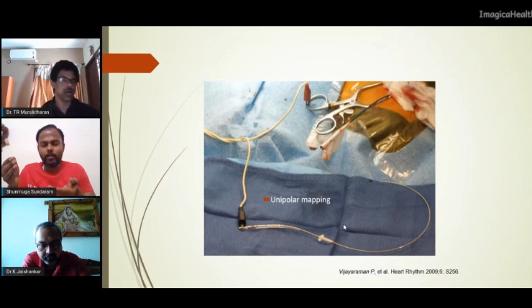this EP system analyzer. There are a few important things which you have to see here. Since only the tip alone is exposed, your anode will still be within the sheath, so you cannot do a bipolar mapping. So you have to go for a unipolar mapping. Meaning you connect one cable to the tip of the lead, and another cable, as you can see here, is connected to the patient's body. This is very important because bipolar will not give you any further mapping, since your anode is still within the sheath. So you have to map in a unipolar fashion.